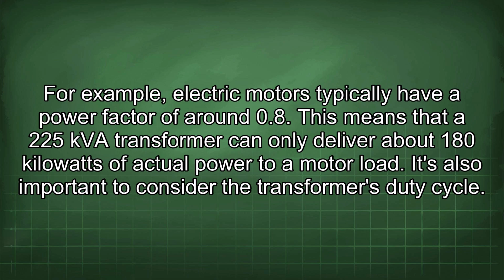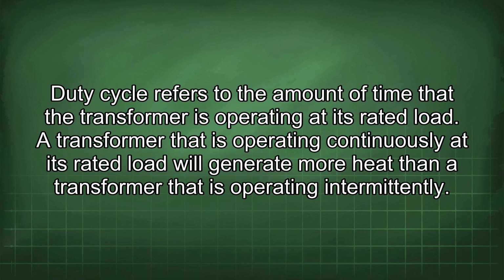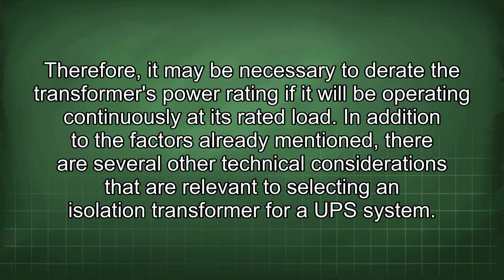It's also important to consider the transformer's duty cycle. Duty cycle refers to the amount of time that the transformer is operating at its rated load. A transformer that is operating continuously at its rated load will generate more heat than a transformer that is operating intermittently. Therefore, it may be necessary to derate the transformer's power rating if it will be operating continuously at its rated load.